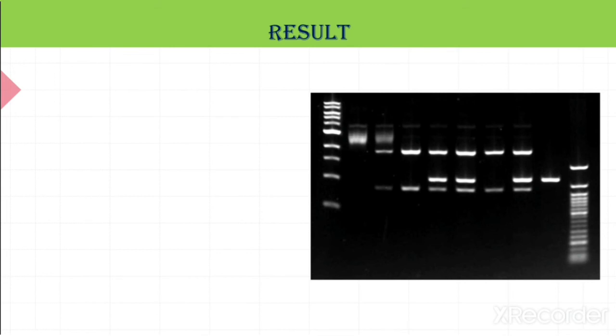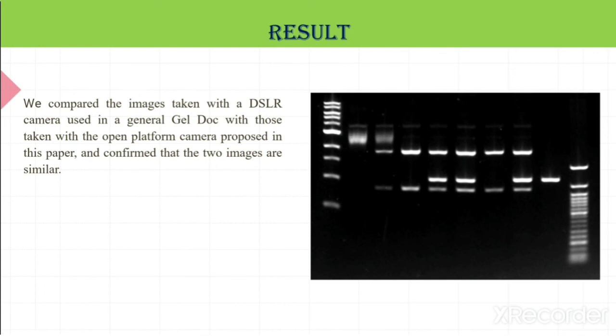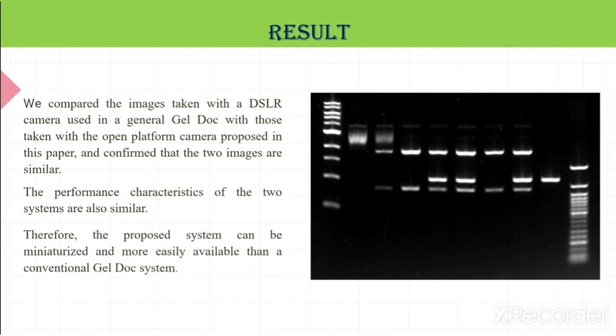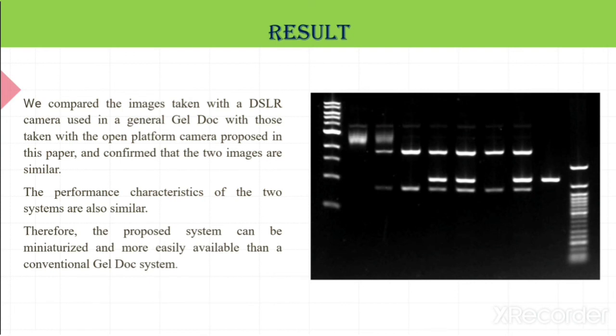These are the results — when you do agarose gel electrophoresis and then use the gel documentation system to see the bands, this is the image which gives us the exact bands of the proteins or nucleic acids under UV light. We compared the images taken by the DSLR camera used in the general gel doc with those taken with the platform camera proposed in this paper and confirmed that the two images are similar. The performance characteristics of the two systems are so similar that the proposed system can be miniaturized and more easily available than the conventional gel doc system.